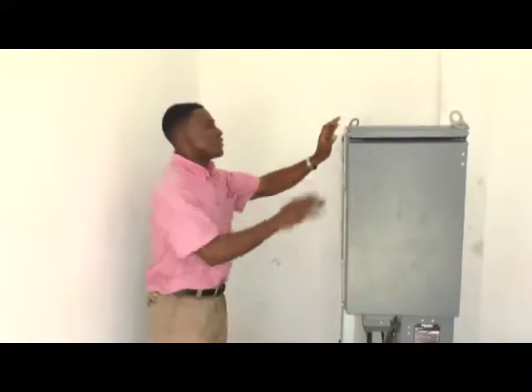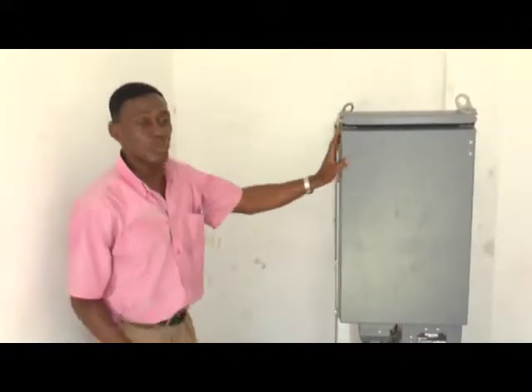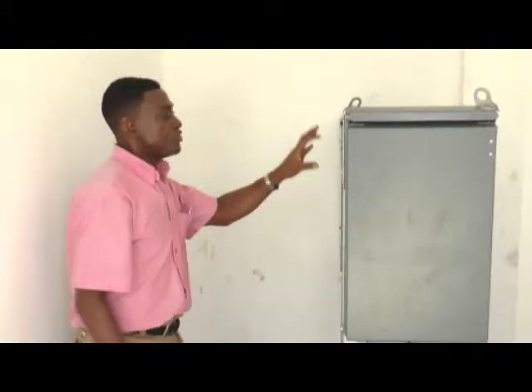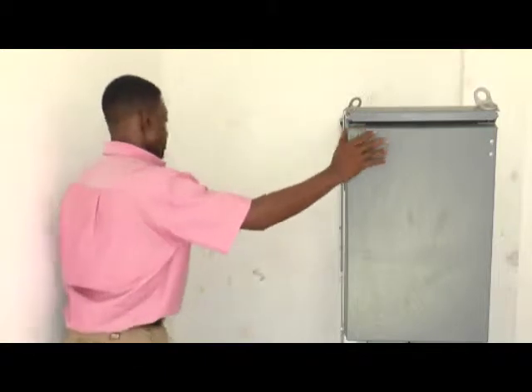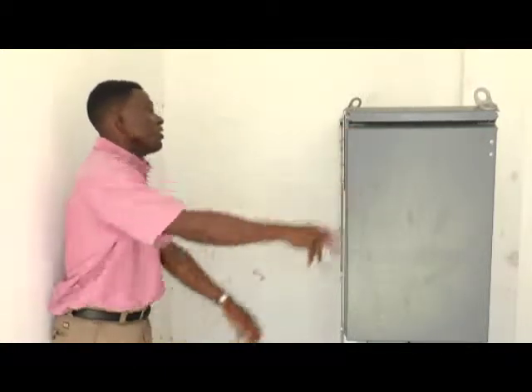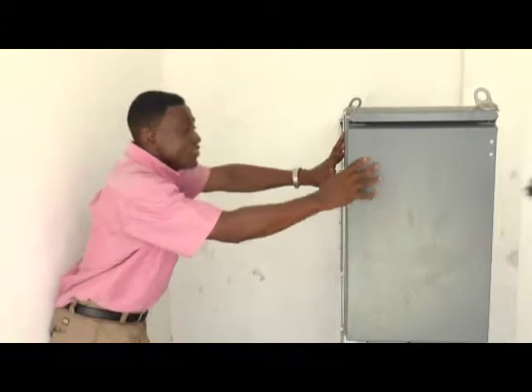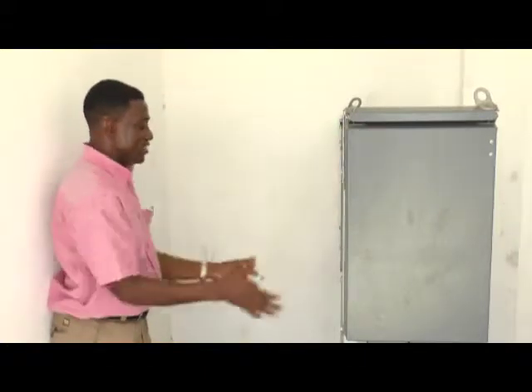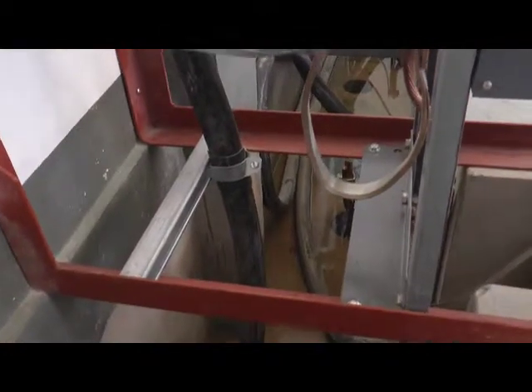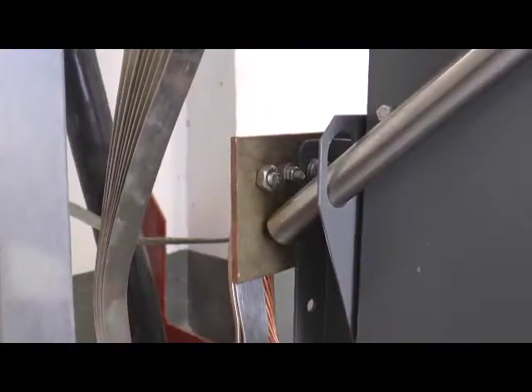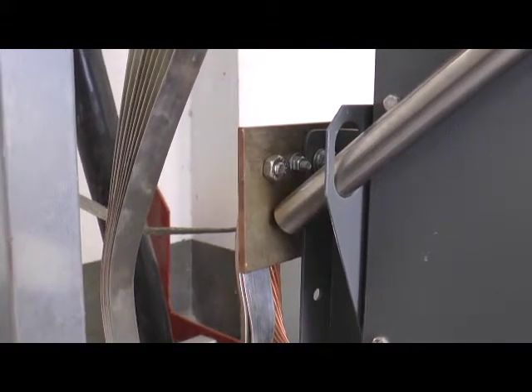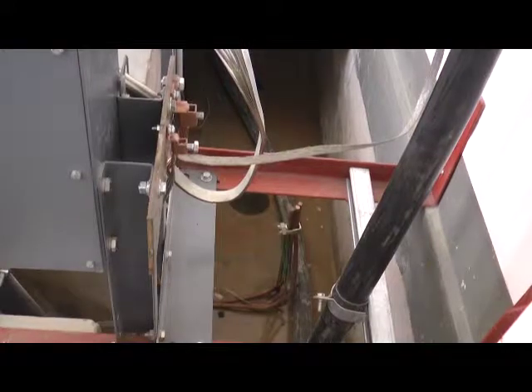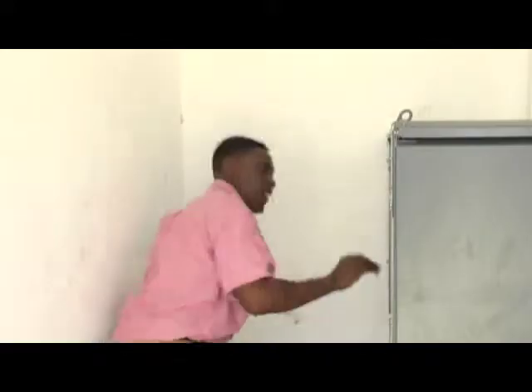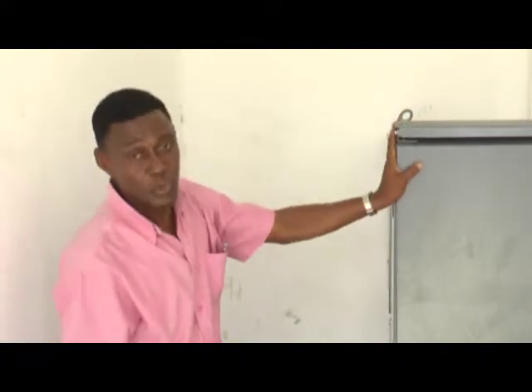This switchgear has all the electrical connections within it. All the current-carrying continuity of the supply voltage of 12,000 volts is stored within this switchgear. This switchgear, this apparatus, must be insulated, isolated from members of the public. The earthing is essential on this installation, as you see driven rods, and the Inspectorate must ensure that all rods, all connections, earthing conductors are properly terminated, and all metal hooks on this apparatus or switchgear are securely connected.